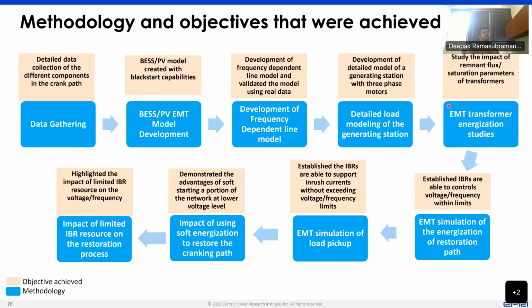So the way we went about the study to look at the black start capability of these inverter resources is, it's very critical that we develop accurate models for this kind of resource. Not just the resource, it's even more important here to develop accurate models of the network, develop accurate models of the transformer, have a good representation of the flux characteristics of the transformer, what kind of saturation we want to enable in the transformer, because if we don't have that representation done in a reasonable manner, then we may miss out on some of the oscillatory behavior that can come up between an inverter-based resource control system and the saturation characteristic of the transformer.